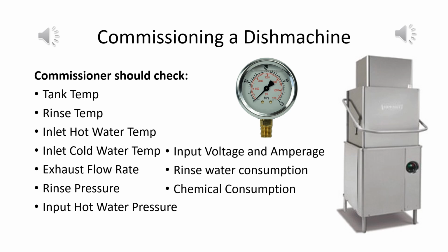The commissioner should also perform a catch and weigh test to ensure all of the water usage is as the manufacturer intended it. If any of these metrics are off, the manufacturer should be contacted and there should be some kind of maintenance performed on the machine. It can also lead to a situation where a machine needs to be replaced. Tank temperatures can range from 120 to 150 degrees Fahrenheit and need to be checked to ensure the proper functioning of the tank's drain system and temperature control.